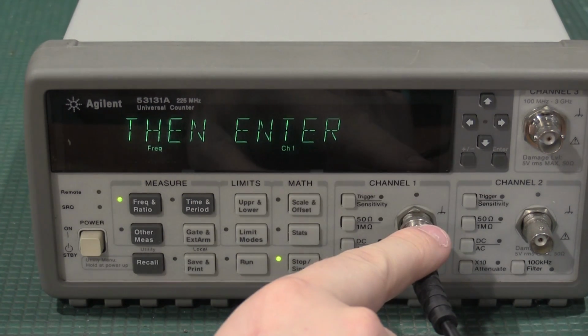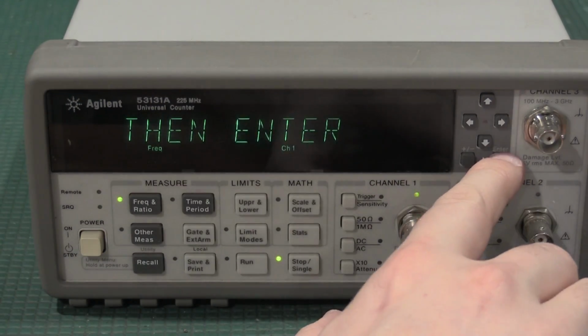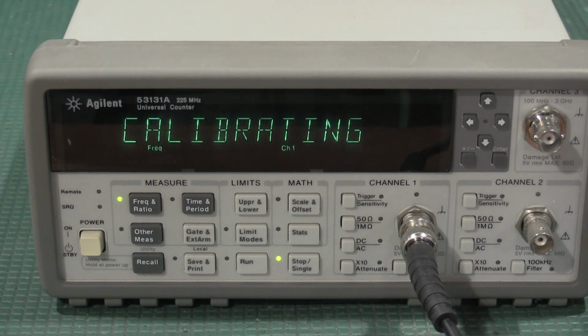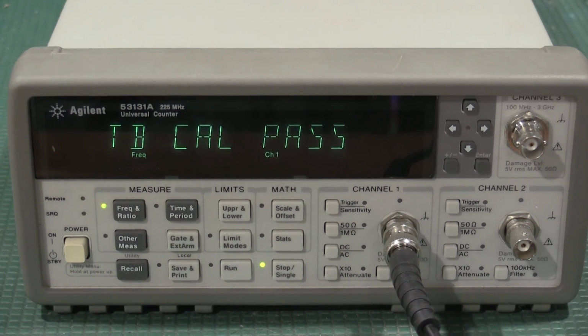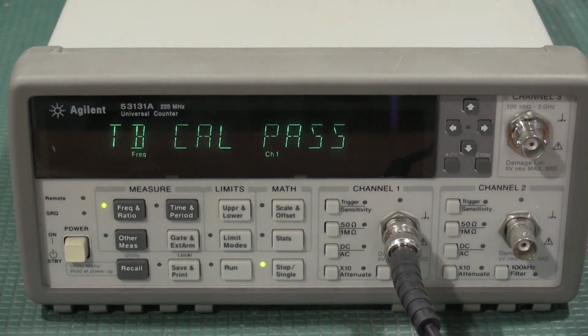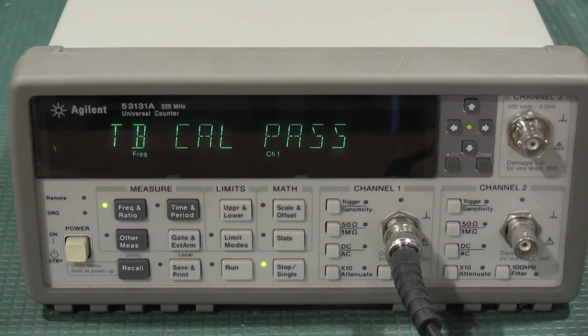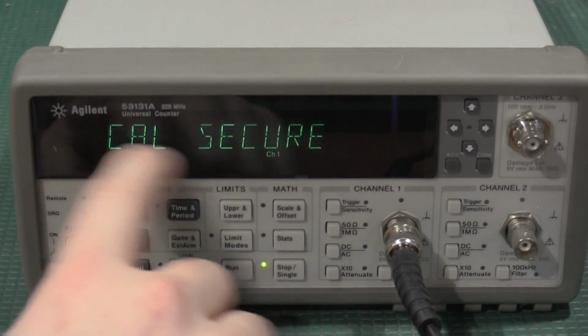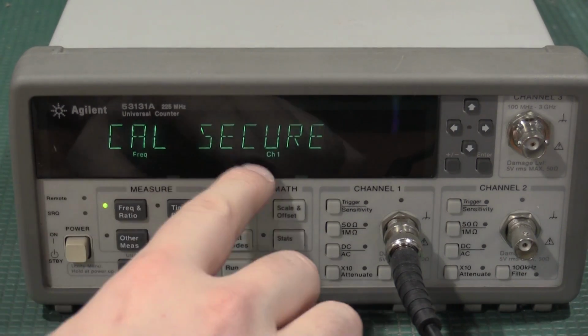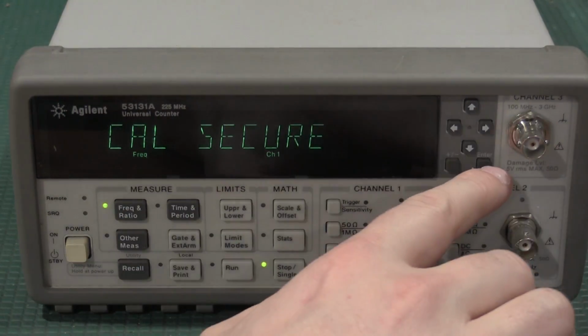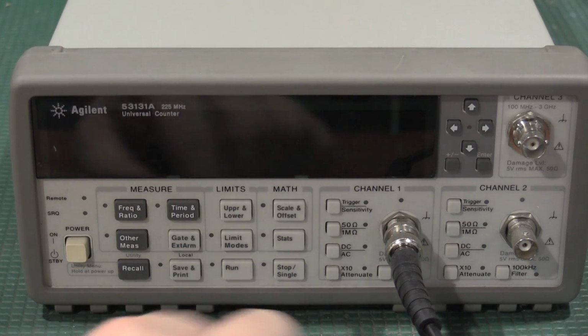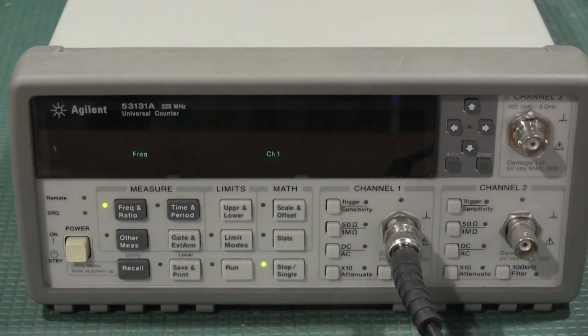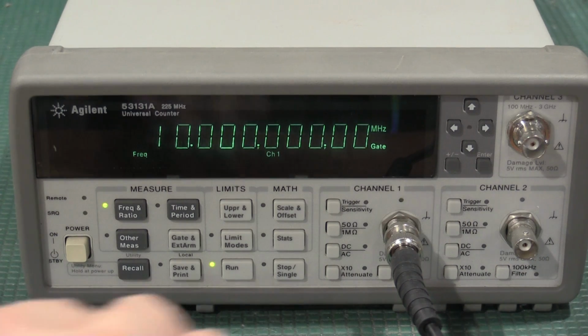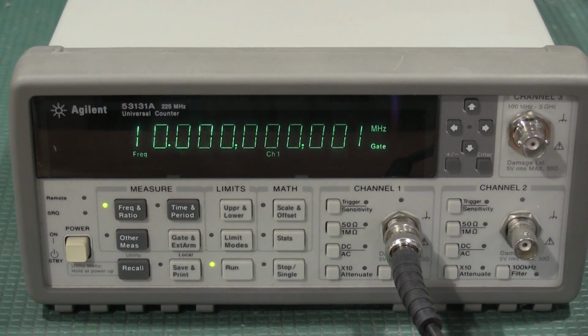Okay, supply 10 megahertz channel 1. This is 10 megahertz off of the rubidium. And enter. Okay, so we have time base calibration passed, which is what we were looking for. And after entering a new code, which can be anything, just remember it, we're back to cal secured. So the time base should be calibrated now. We'll turn this off, turn this back on. We should see closer to 10 megahertz. Well, that looks better. Well, I would say that's going to be a success.